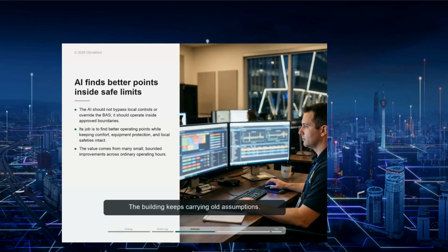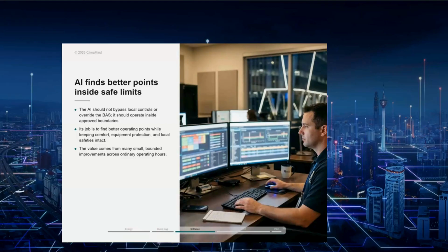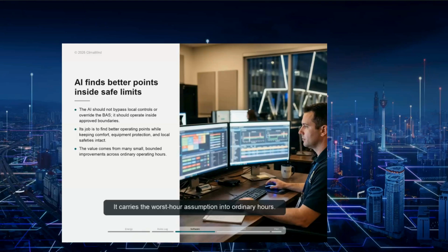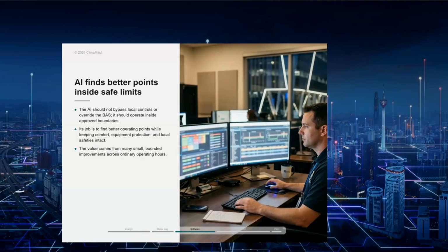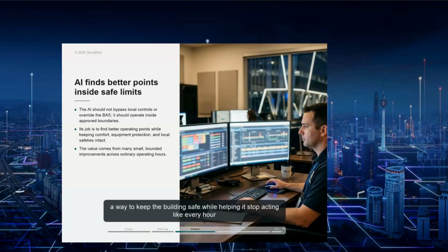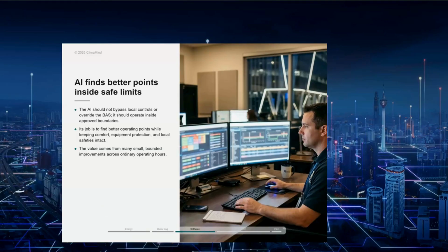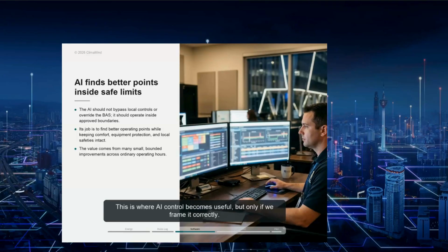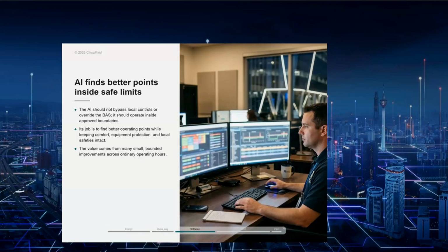The building keeps carrying old assumptions. It carries the morning assumption into noon. It carries the 2 p.m. assumption into 4:30 p.m. It carries the worst hour assumption into ordinary hours. That is the need, a way to keep the building safe while helping it stop acting like every hour is peak load. This is where AI control becomes useful, but only if we frame it correctly.